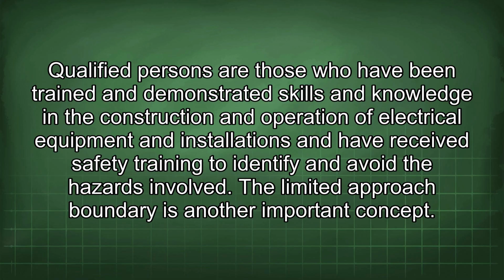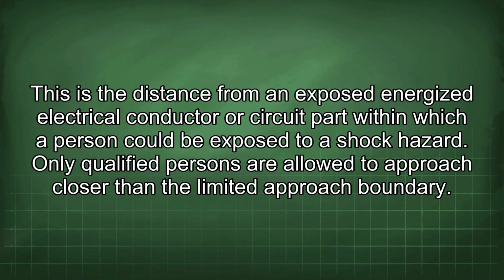The limited approach boundary is another important concept. This is the distance from an exposed energized electrical conductor or circuit part within which a person could be exposed to a shock hazard. Only qualified persons are allowed to approach closer than the limited approach boundary.